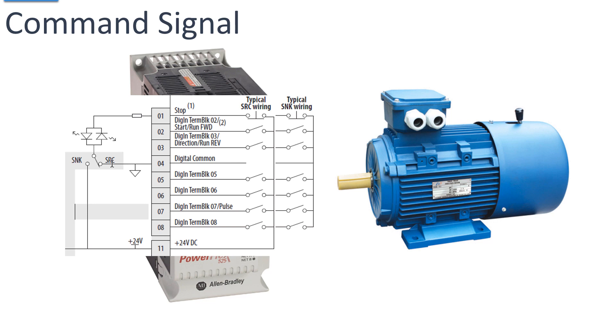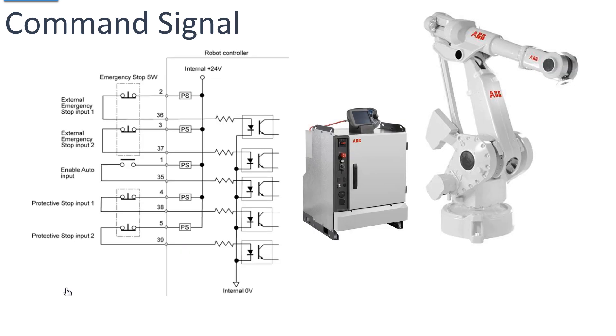Digital input terminals five, six, seven, and eight can be programmed to be whatever you want. The PLC would send signals — close contacts — feeding 24 volts DC to these terminals to control the drive.